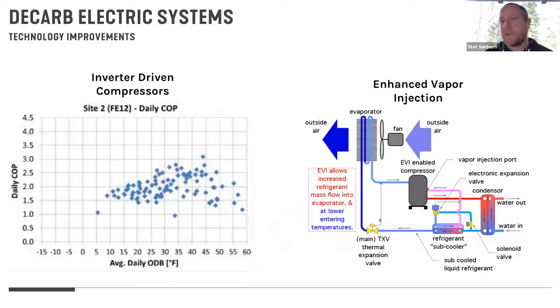And the idea here is to subcool it before it goes through its expansion valve, before it is released and drops down in temperature. So by removing even more of that heat first, we can subcool the refrigerant before it goes into our evaporator. And this is really important for two reasons. One, as the outside ambient temperature is dropping, that delta T between the refrigerant and the outside air temperature is getting awfully close. In some circumstances, they're so close that you're not going to effectively get heat pulled out from the outside air. It's just not enough difference. And so by subcooling the refrigerant far below the outside ambient air temperature, we're able to push that delta T farther apart, so it still has room to pick up energy before it goes back to the compressor.